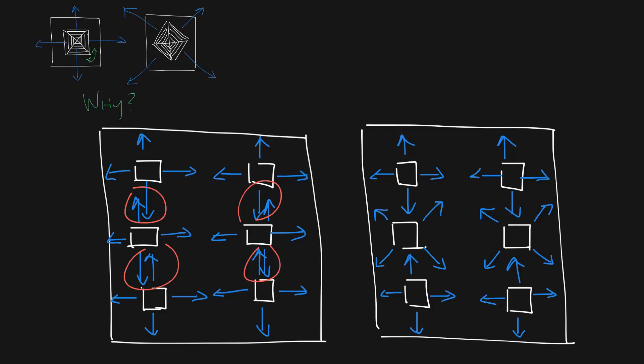And now you don't have any colliding air streams in your space. So the answer to why you would want to have a corner blow is that you could get high airflow without having colliding air streams.